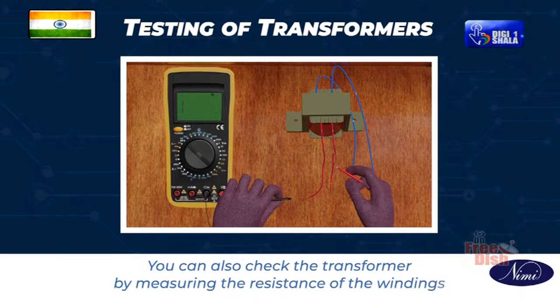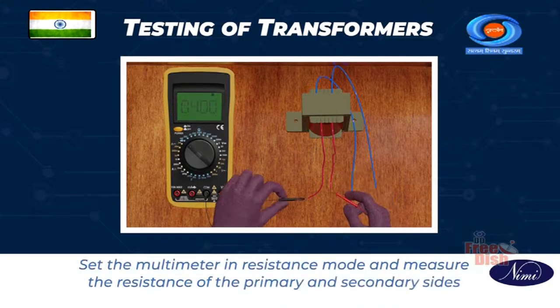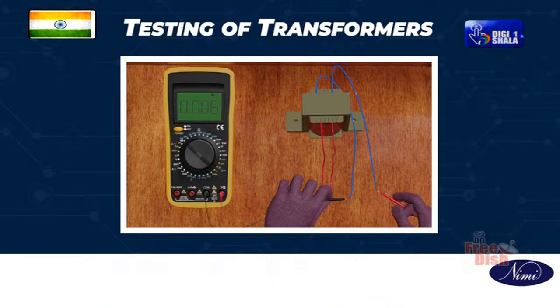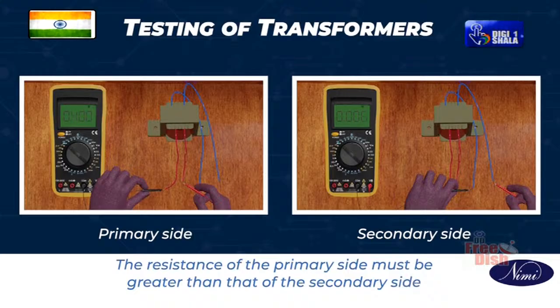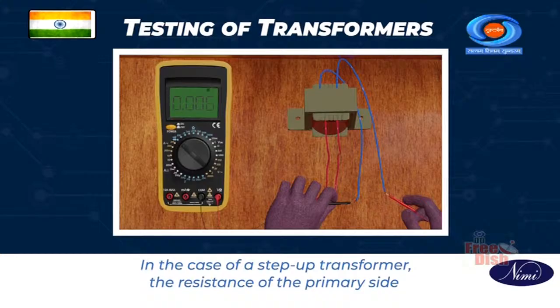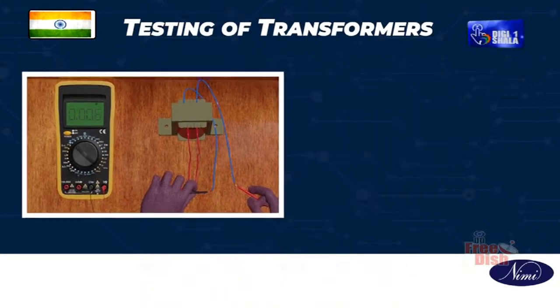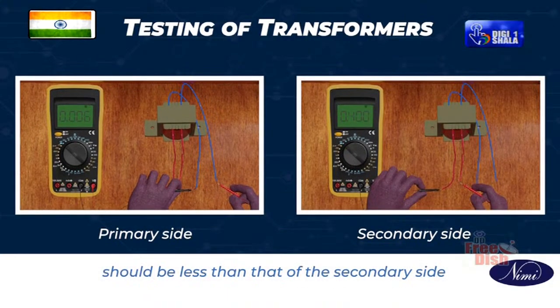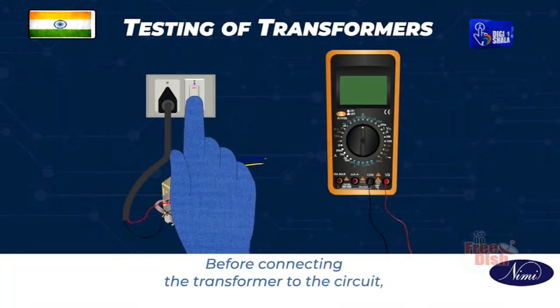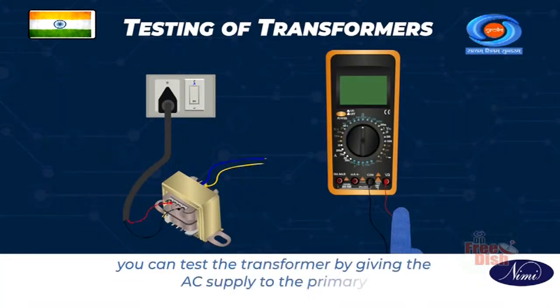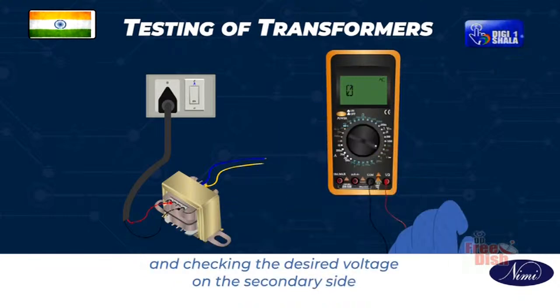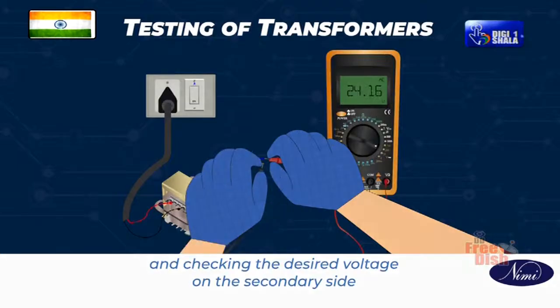You can also check the transformer by measuring the resistance of the windings. Set the multimeter in resistance mode and measure the resistance of the primary and secondary sides. The resistance of the primary side must be greater than that of the secondary side. In the case of a step-up transformer, the resistance of the primary side should be less than that of the secondary side. Before connecting the transformer to the circuit, you can test the transformer by giving the AC supply to the primary and check the desired voltage on the secondary side.